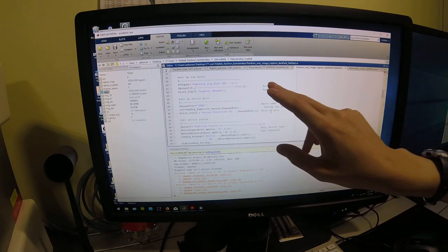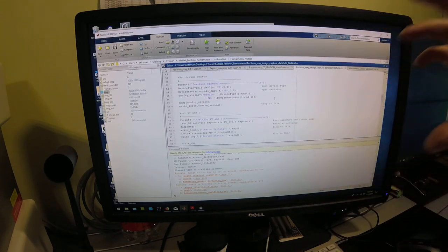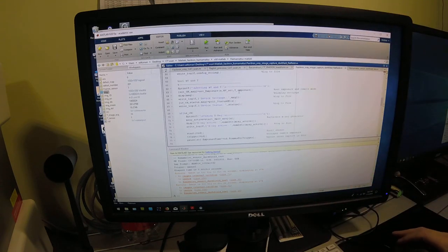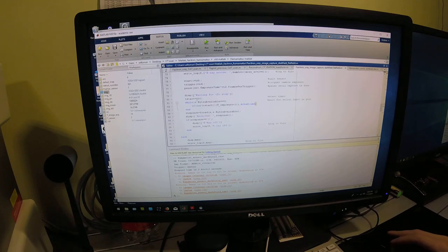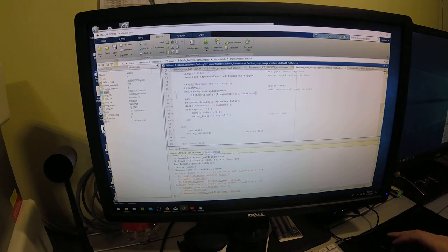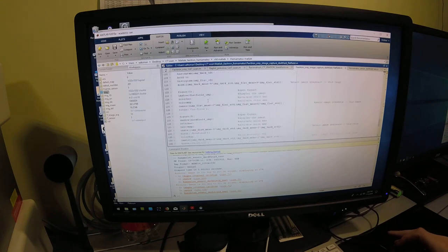So what it does is take the dark field images and then the flat field images. It sets up the X-ray generator, opens the COM port, and sets up the X-ray system to generate an X-ray exposure over however many frames you want to average over and however much integration time. It runs through it, triggers the flat panel detector, and waits until the image is captured. Then the X-ray generator will shut down, and it will get the image data and reprocess that.